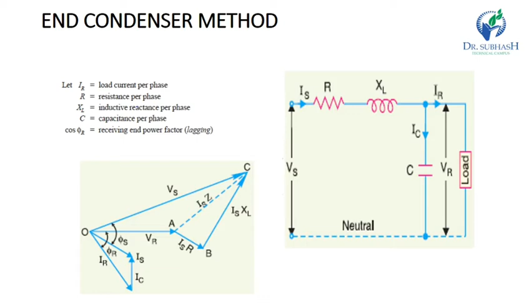Now we calculate the medium transmission line using the end condenser method. Here we use the capacitance at the end side of the transmission line, or the receiving end side. Now with the help of a phasor diagram, we can calculate the sending end voltage, sending end current, and sending end power factor with the end condenser method. Now we see the procedure to find the sending end voltage, sending end current and sending end power factor with the end condenser method in a medium transmission line.